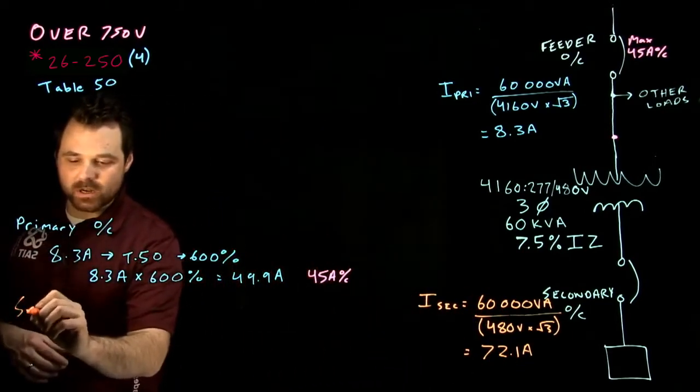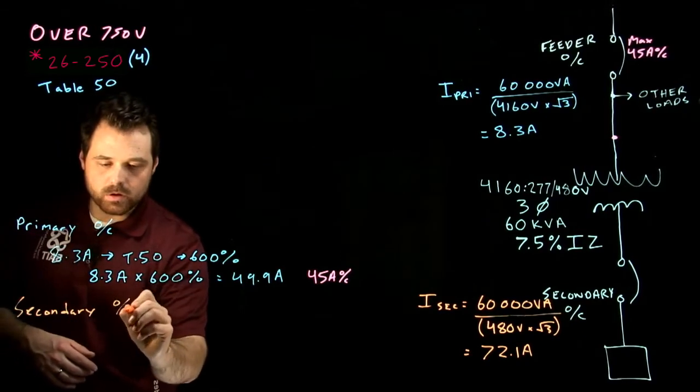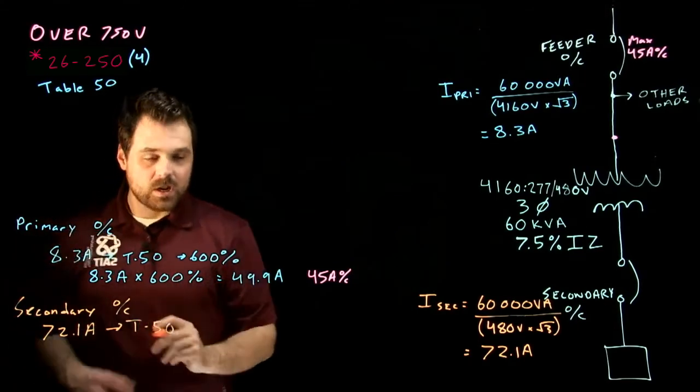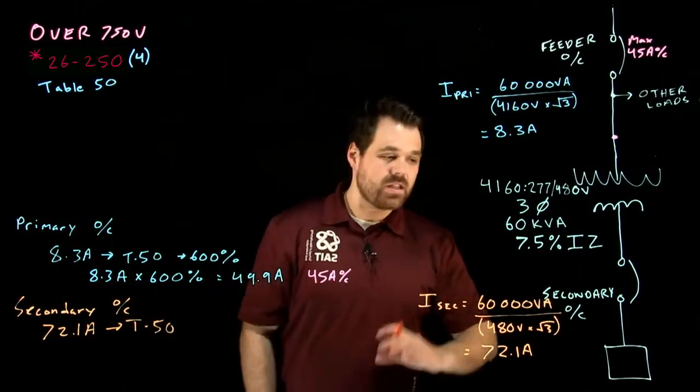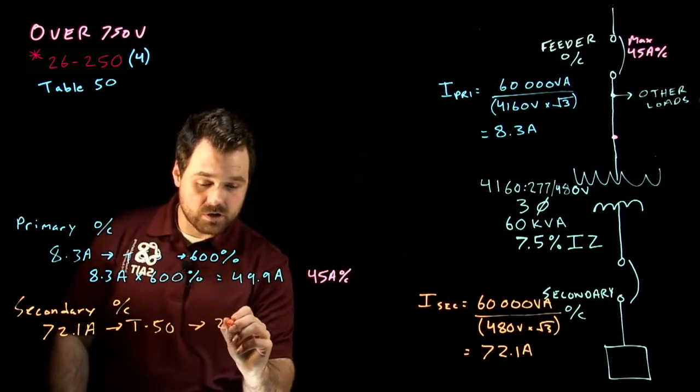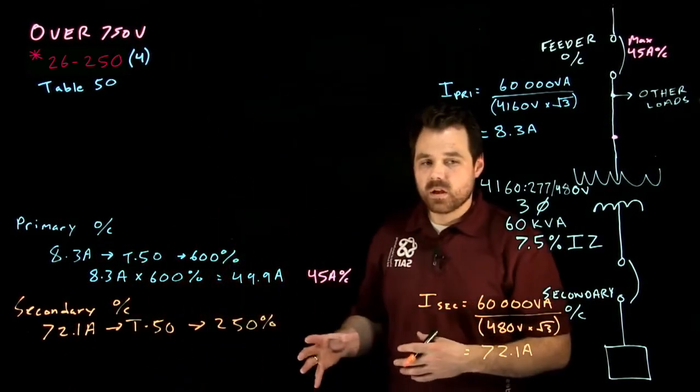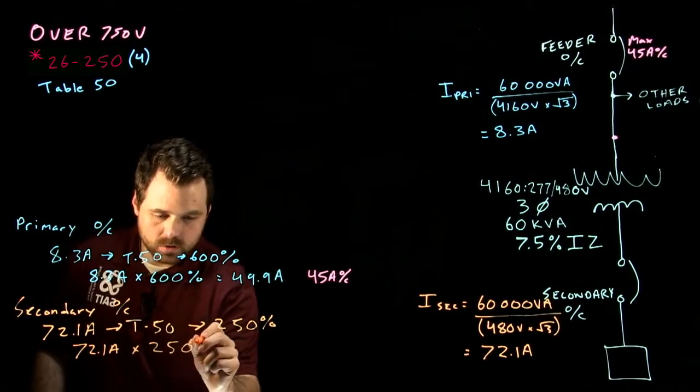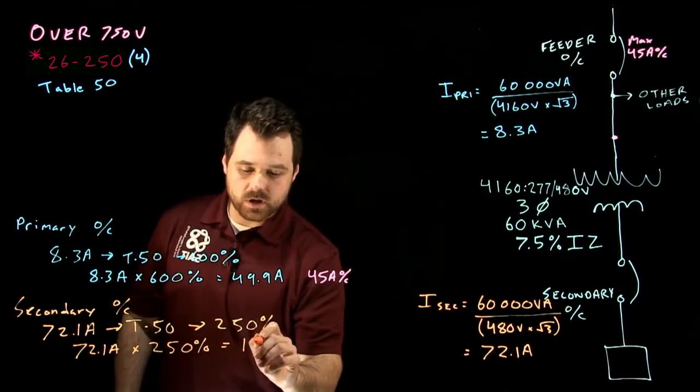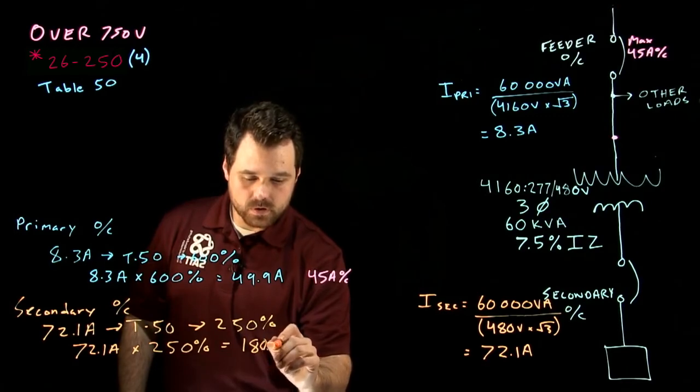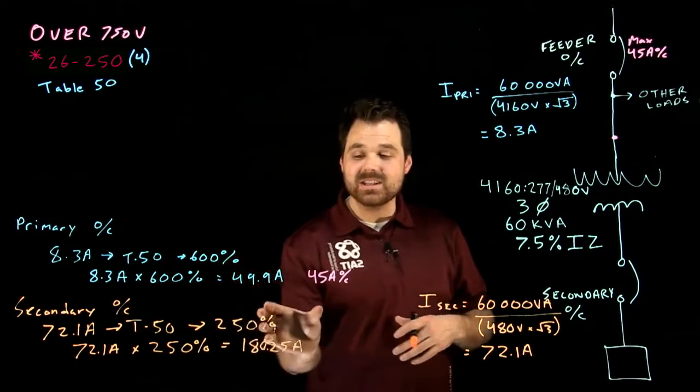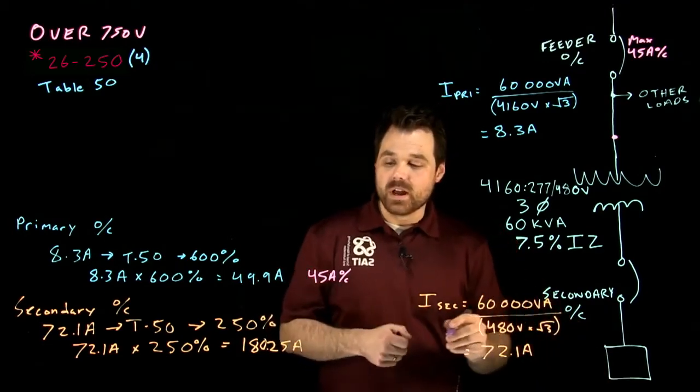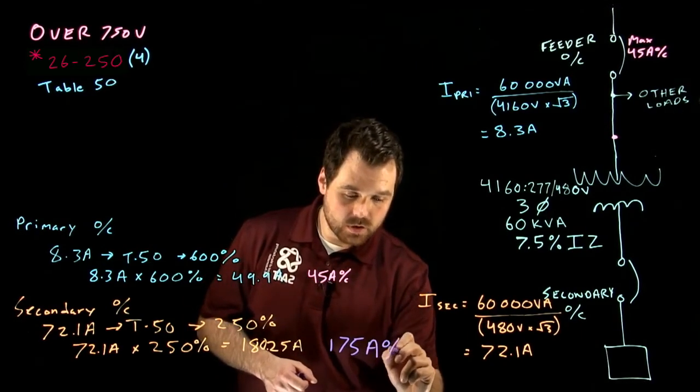With that information, for our secondary OC, we're going to take our 72.1 amps and take that to table 50. Now, based on our 7.5% IZ and the voltage, and the fact that we are using a circuit breaker, it tells us we can use 250% of the rated secondary current. So we go 72.1 amps times 250%. That is going to give us 180.25 amps. Our overcurrent cannot exceed this value, much like the primary, which means when we go to table 13 to size our overcurrent device, we are going to end up with a 175 amp OC on the secondary.